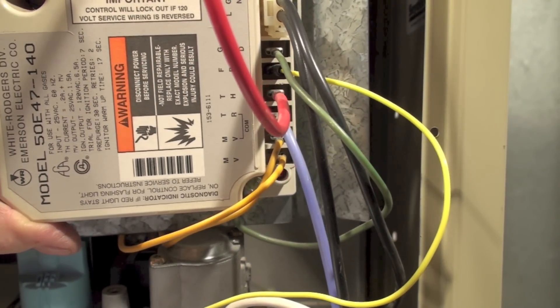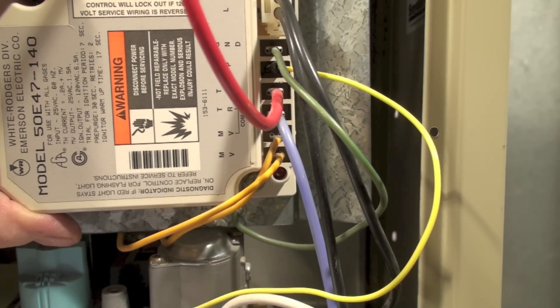With a flashing light, the unit has tried three times and failed to light. That blinking code is the only code this control has. It is a red light — it doesn't look very red on this camera — and it's blinking like that. If it's steady, it means the control has internally failed. That is the White-Rodgers 50E47 control.